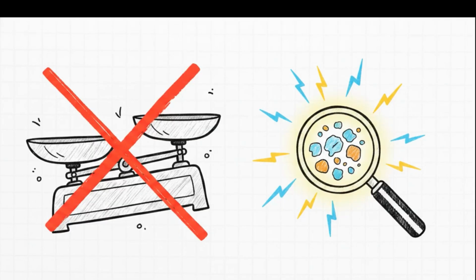So because of all that, we really need to frame DLS accurately. It is technically considered a non-calibrated or semi-quantitative analytical method, right? It is not a rigidly calibrated scale like you'd find weighing out turkey at a deli. Instead, it's this incredibly powerful analytical tool that gives us rapid, deeply useful information about particle size distributions, all based strictly on the physics of the sample itself.